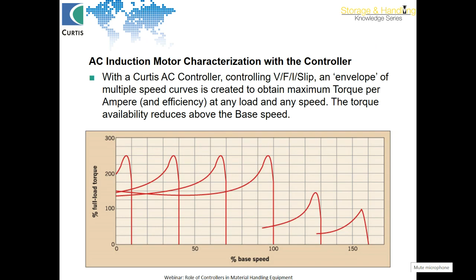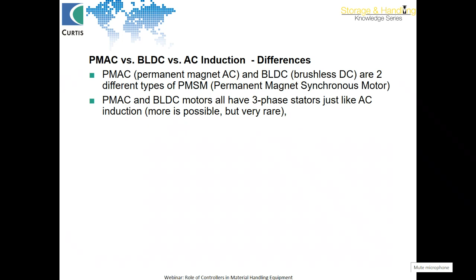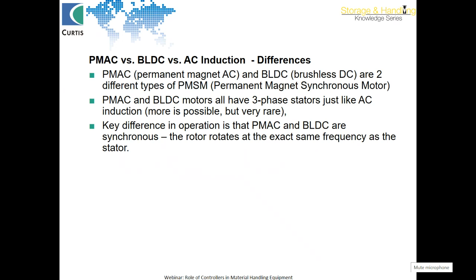This slide shows the permanent magnet AC motors versus brushless DC motors versus AC induction motors. Basic differences: the permanent magnet AC motors and the brushless DC motors both employ magnets. They are two different types of permanent magnet synchronous motors. They are synchronous motors where the rotor and the stator speeds are the same. They also have three-phase stators, just like the AC induction motor. The key difference is that they are synchronous because the frequency of rotation of the stator electric field and the rotor mechanical motion are the same.